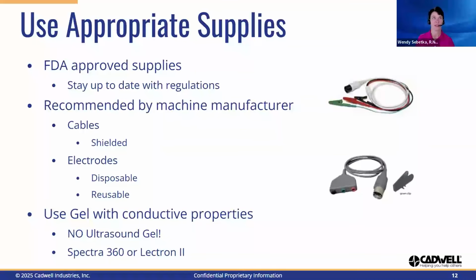Another key to preventing noise is using appropriate supplies. All supplies should be FDA approved. FDA regulations do change, so it is important to stay up to date on these regulations. While it is not required, it is suggested to use supplies that are recommended by the machine manufacturer, as these are the supplies that have been through testing and validation processes. Shielded cables, like the ones shown on the slide, have an extra conductive layer around the wires to protect against electromagnetic interference and can be helpful in preventing noise.